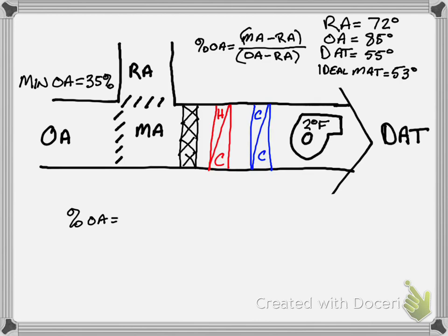Now our ideal mixed air temperature has not changed. We are still trying to make 53, but now we have a new equation to plug in. We have 53 minus 72 over 85 minus 72, which comes to be negative 19 over 13.